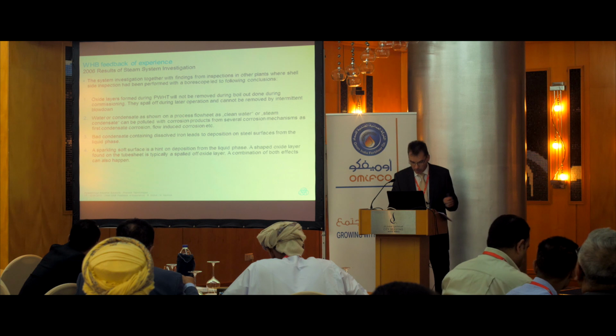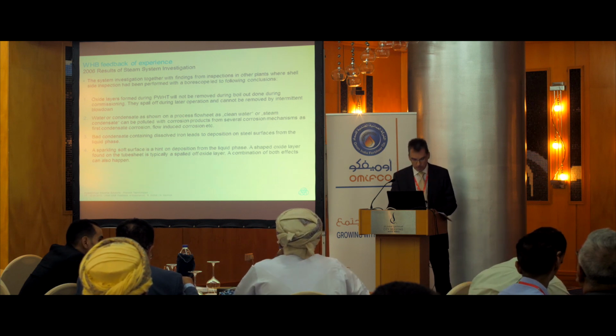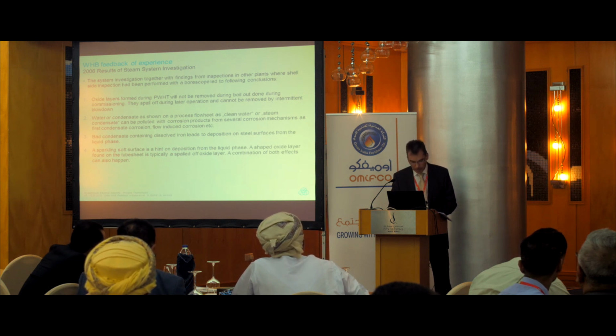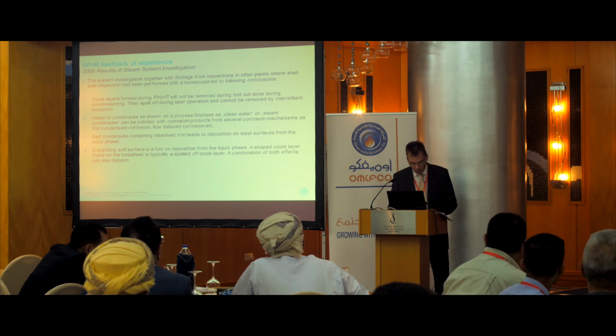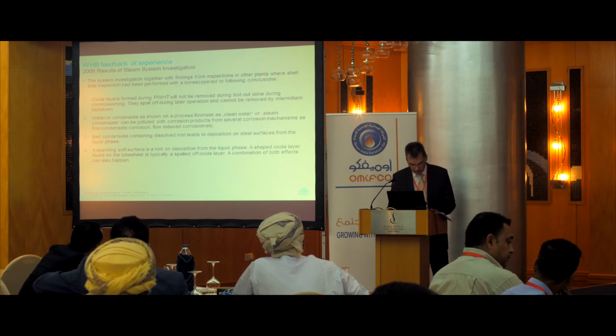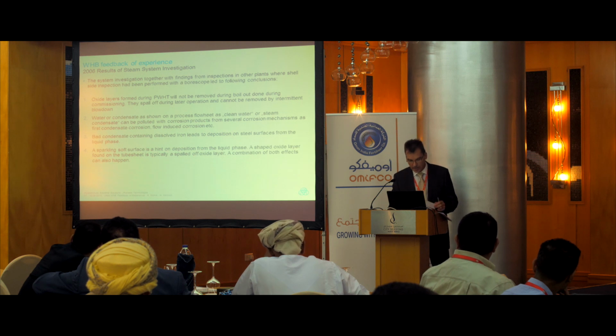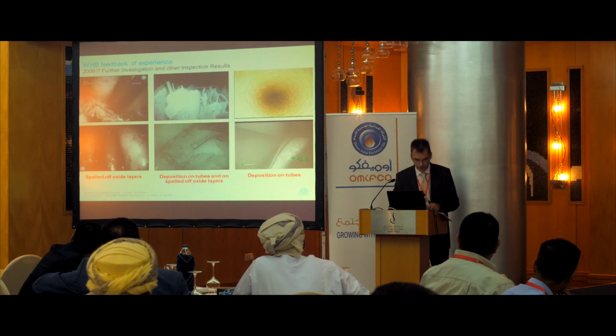Also, evidence was found that corrosion upstream of the boiler leads to iron deposits in the boiler due to the changing solubility when the boiler water is evaporated. This leads to porous deposits in which impurities in the boiler water can concentrate and form local corrosion elements. And more inspections inside the boilers have been performed for further evaluations, as examples shown here.